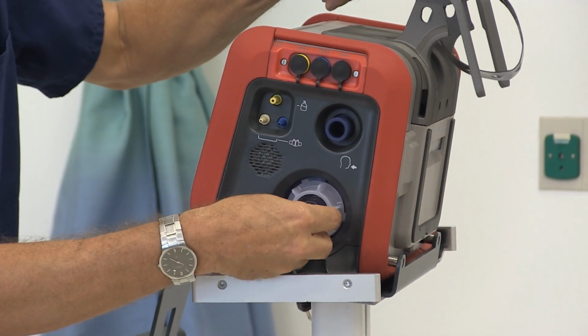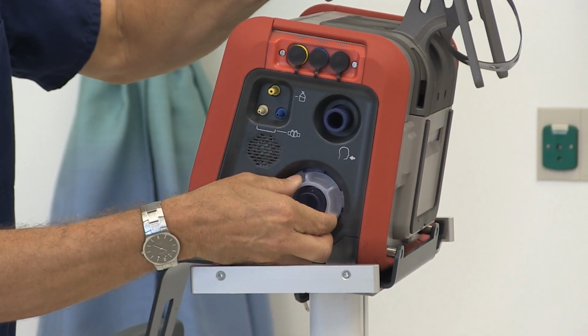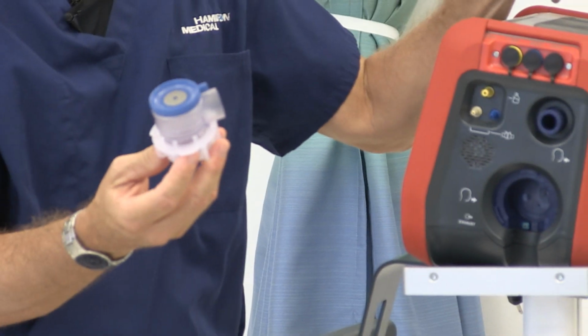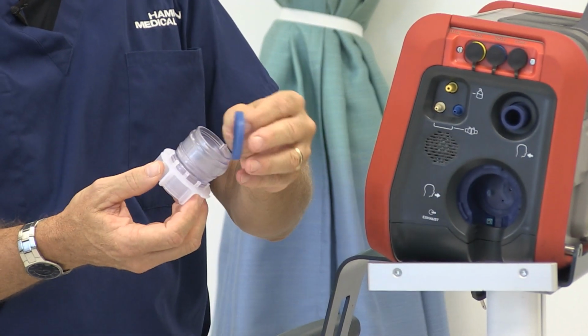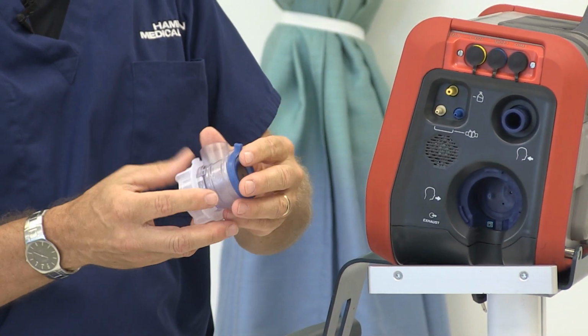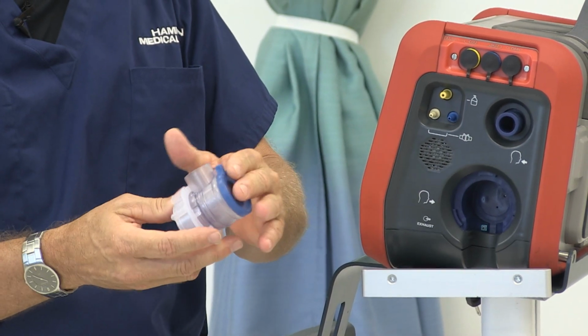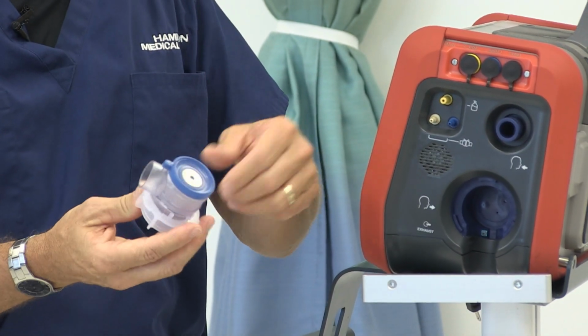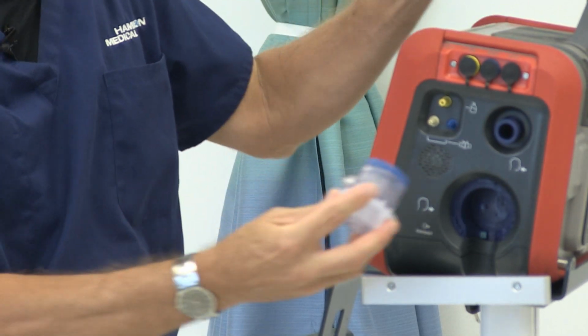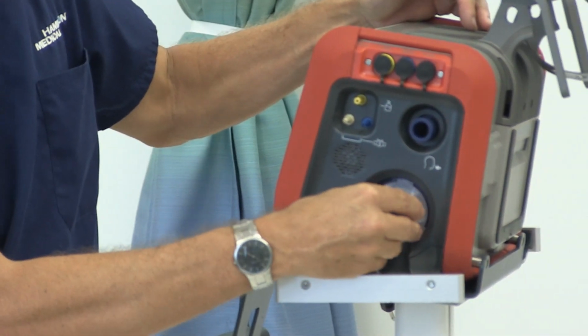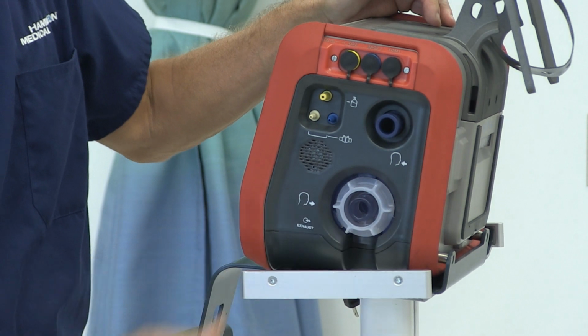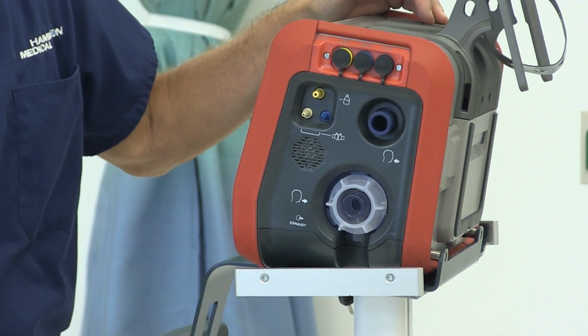To check the expiratory valve, just give it a turn counterclockwise, and it pops right out. It has a diaphragm and a plastic housing. Make sure the diaphragm is aligned and smooth around the edges. To replace it, pop it in, give it a turn clockwise.